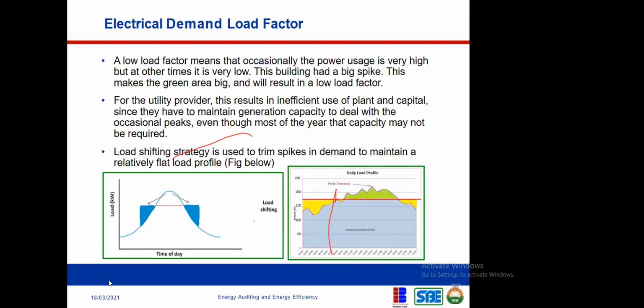Okay, so what that means is, if you have a 20 kVA generator, you can go as high as 18, maybe just for a few minutes, and then you come down again to about 12 or 10. So you've created a spike. Maybe you've added a heavy load that created a spike. Now that spike is actually what is going to determine the capacity of generator that you're going to buy, even if you create that spike only once in a year. Otherwise, if you undersize the generator and you create that spike, your system will go down. So it is important when you're sizing a generator to look at what could possibly create spikes and how you can eliminate those spikes.